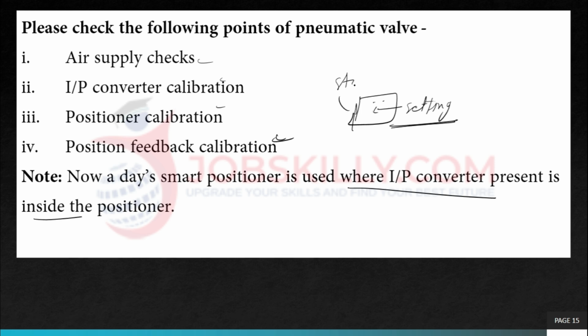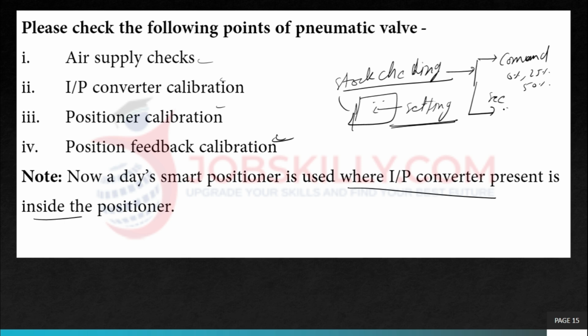We will do stroke checking. In stroke checking what will we do? We will give commands like 0%, 25%, 50%, and we will see its opening. If we give a 25% command, then it should open 25%. If it is not opening, then we will do the calibration. This is the stroke checking.